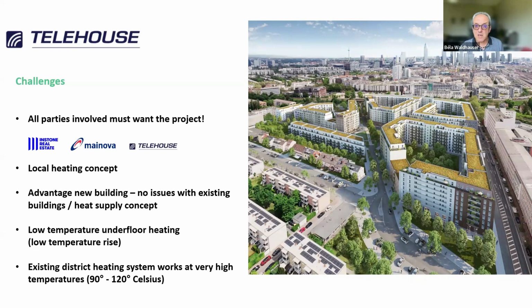In that case, as mentioned, it's a local heating concept, which makes it much easier because of the very low temperature provided by a data center. And the advantage is, in that case, it's a new building. So there's no existing heating concept, no supply, and you can start from scratch. Because it's a new building, they have underfloor heating, which works at low temperatures.